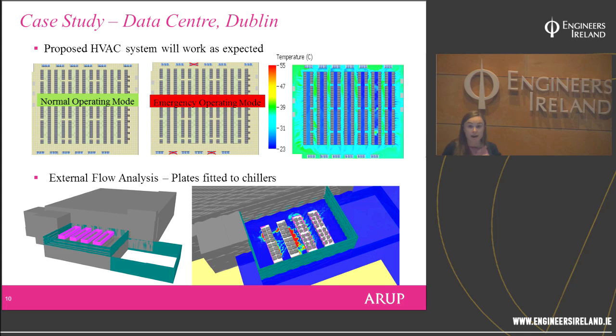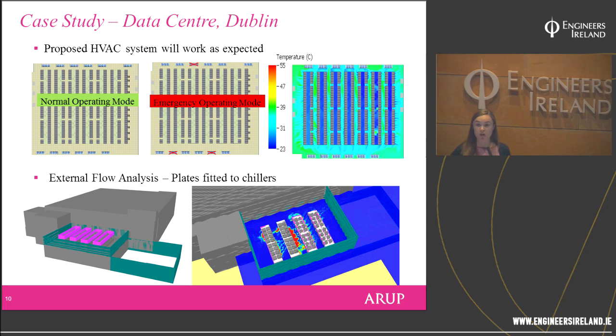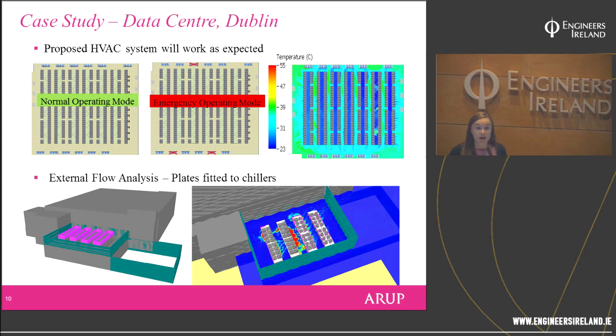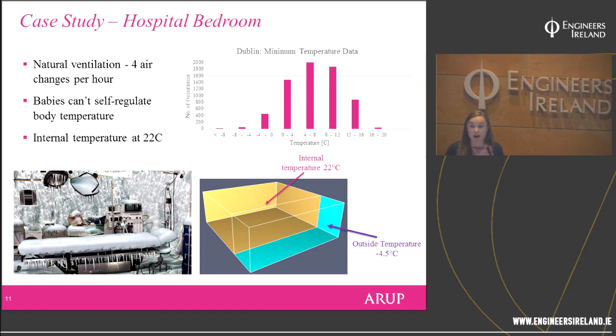As additional work, we did an external flow analysis. It was suspected the external chiller units were not performing efficiently, with outflow getting sucked back in as inflow. The contractor suggested adding plates to separate outflow and inflow. We efficiently added these plates to our model and found there would still be significant problems. Before the client or contractor spent any significant money on remedial works, we demonstrated it would not be an effective solution.